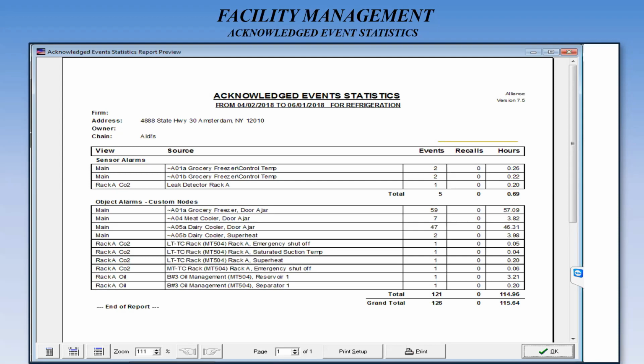So if you acknowledge an alarm but the condition does not improve, it's just a simple acknowledgement, and the alarm is going to come back and pester you or nag you to say, hey, you didn't solve this, you still have an alarm problem in the system. We're different in the way we do alarms. We don't want them to just magically disappear because somebody shut it off. They can silence it or acknowledge it, but if the problem is not solved, it's going to recall and another alarm is going to be generated. I hope that was clear.